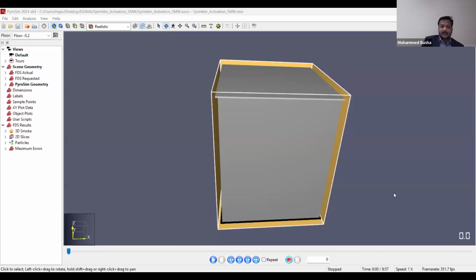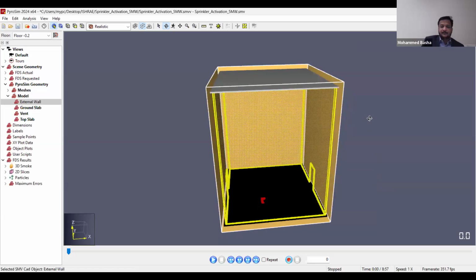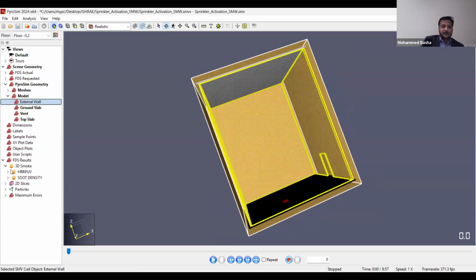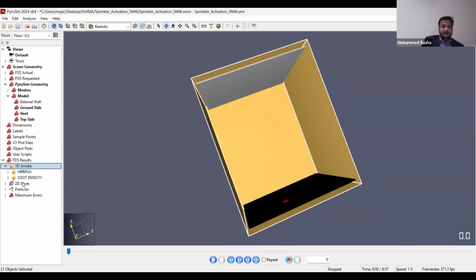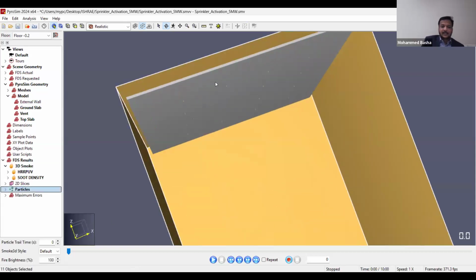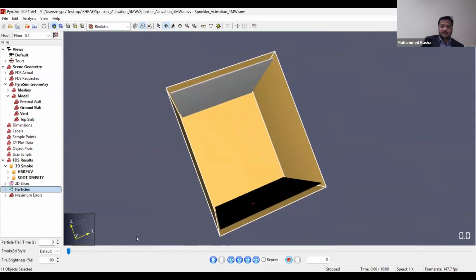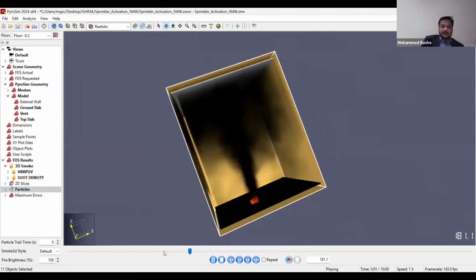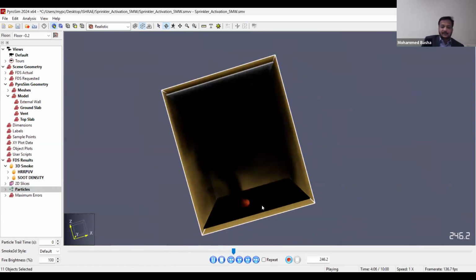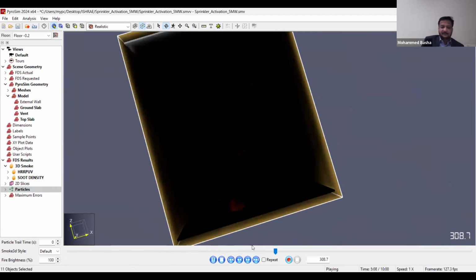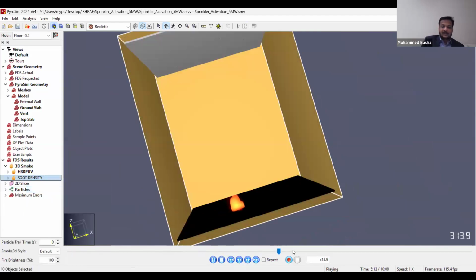Okay, you can see here the same room, but I used a 5 megawatt fire. Okay, here also the same. You can see sprinklers. It's a 4x4 configuration, 4 meter by 4 meter. Now here also smoke is coming. Still, I have some clear height here. Let me see whether the sprinklers are activated or not. Not yet. See, it activated at somewhat 440 seconds.